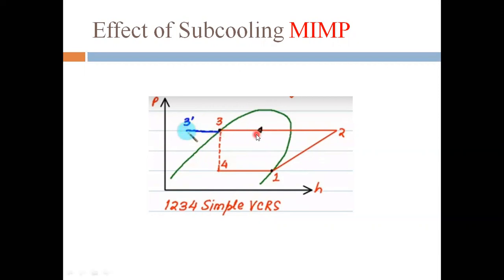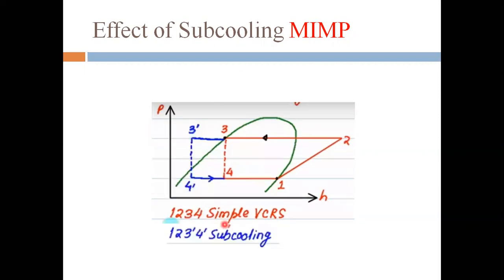We are not changing any condenser pressure or suction pressure, so the pressure lines remain the same. We are doing the sub-cooling by having extra water or by lowering the temperature of the water used for condensation. Point three shifts to three-dash, then expansion gives three-dash to four-dash, and evaporation four-dash to one is the refrigerating effect. The red cycle is the simple VCRS — one, two, three, four — and by doing sub-cooling, two new points are generated: three-dash and four-dash.